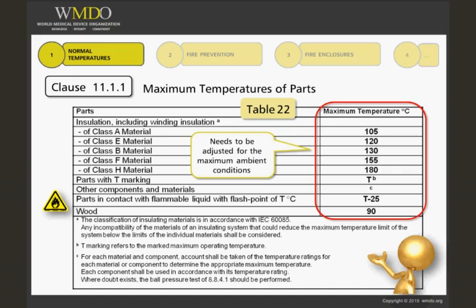The table also specifies components marked with a temperature rating, such as capacitors and other parts, which would use the maximum operating temperature for that component. Next, we have parts in contact with flammable liquids, where the limit is 25 degrees Celsius less than the flashpoint of the liquid. Finally, we have wood, where the specified limit is 90 degrees Celsius.